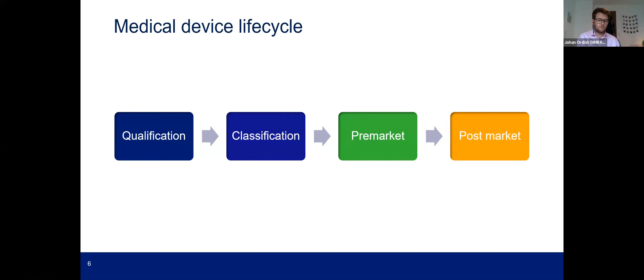You also have the pre-market phase, what you have to assemble before you go to market. In very broad general terms, what it requires is that you demonstrate conformity with the essential requirements. They're in Annex 1 of the Medical Device Directive. And also that you have a clinical evaluation report, which demonstrates that the device has an acceptable risk-benefit ratio and provides further evidence. And post-market, you're required to keep track of your device, what it's doing, when it's going wrong, and so on. So there are dynamic duties that apply to you as a manufacturer. So I'll go through some of those in more detail now as well.